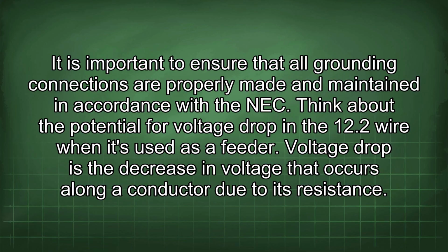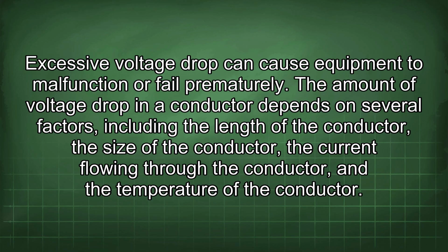Think about the potential for voltage drop in the 12.2 wire when it's used as a feeder. Voltage drop is the decrease in voltage that occurs along a conductor due to its resistance. Excessive voltage drop can cause equipment to malfunction or fail prematurely. The amount of voltage drop in a conductor depends on several factors, including the length of the conductor, the size of the conductor, the current flowing through the conductor, and the temperature of the conductor.